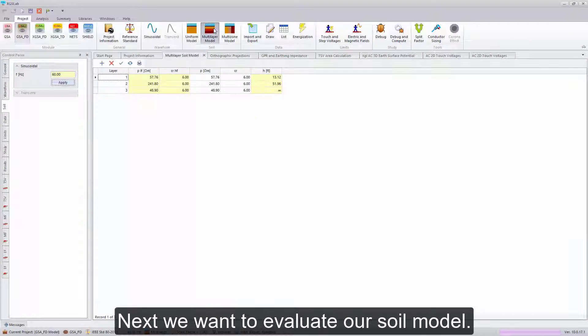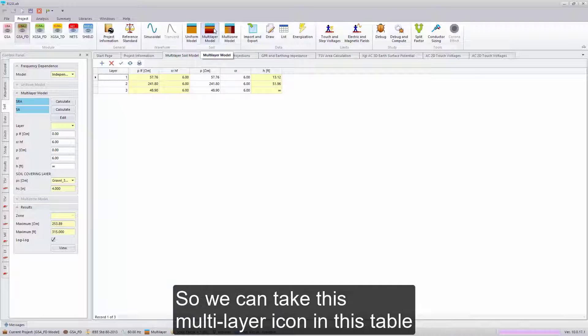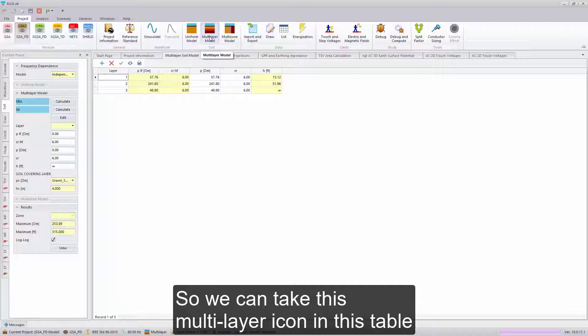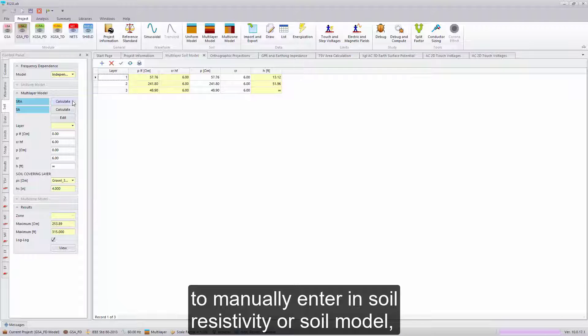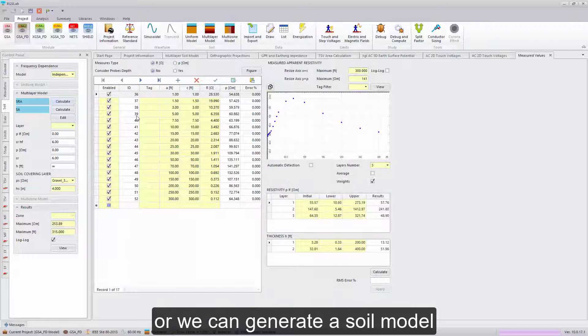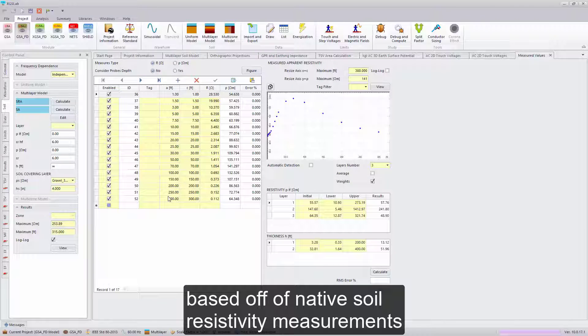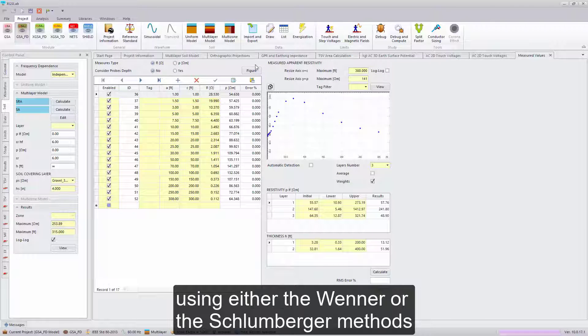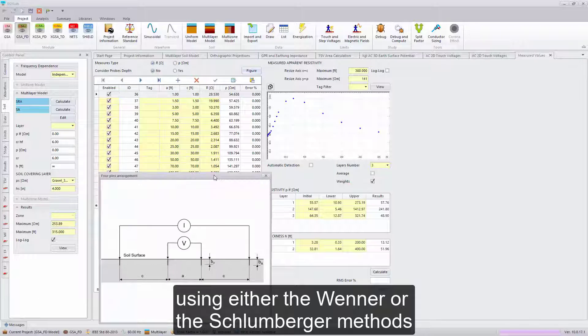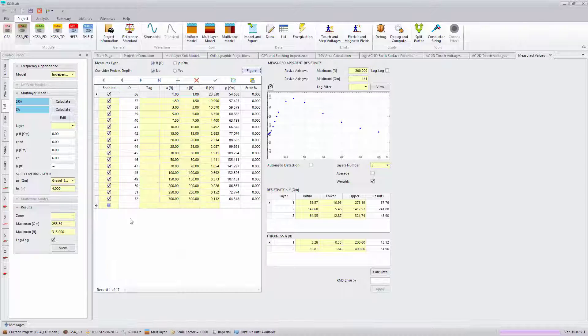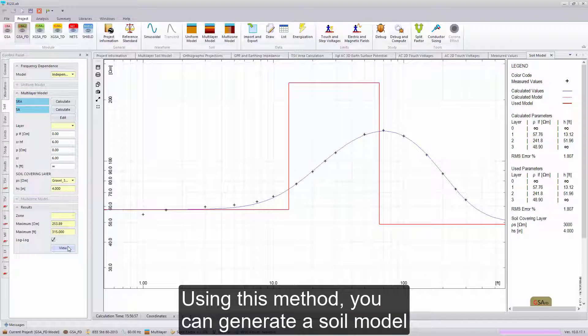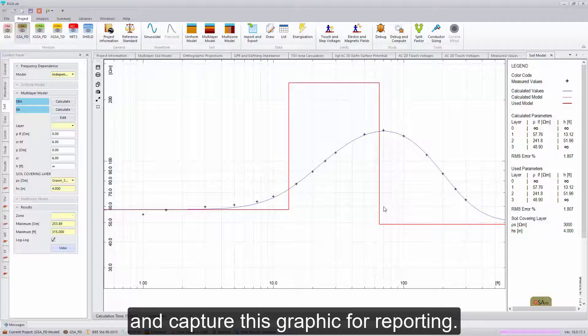Next, we want to evaluate our soil model. We can take this multi-layer icon and table to manually enter in soil resistivity or soil model, or we can generate a soil model based off of native soil resistivity measurements, using either the Wenner or the Schlumberger methods following the spacings provided below. Using this method, you can generate a soil model and capture this graphic for reporting.